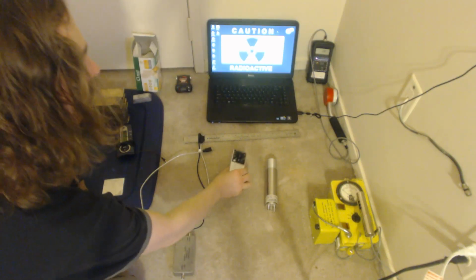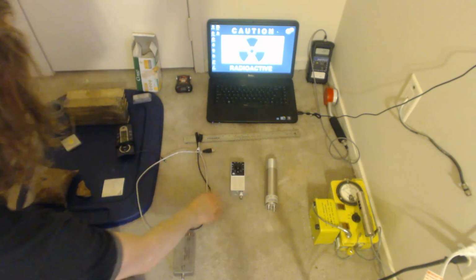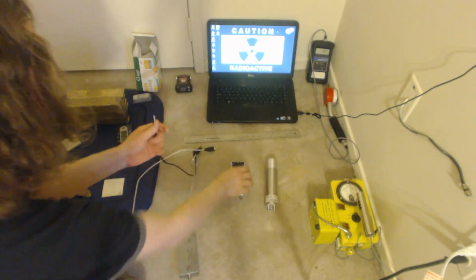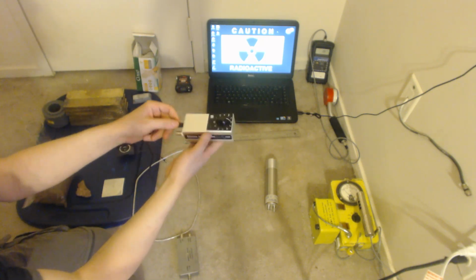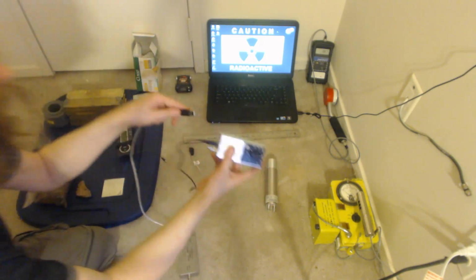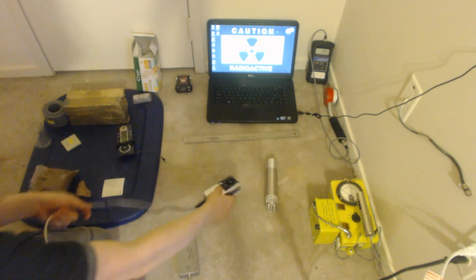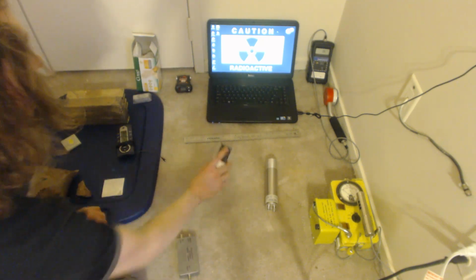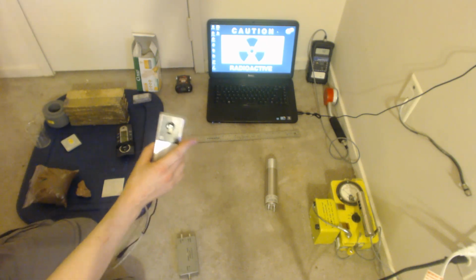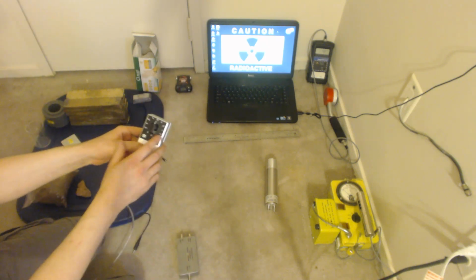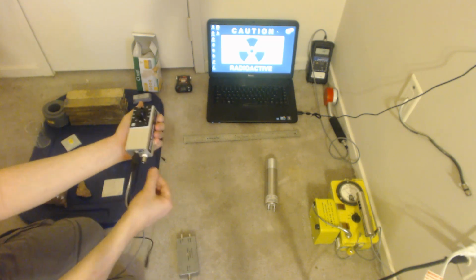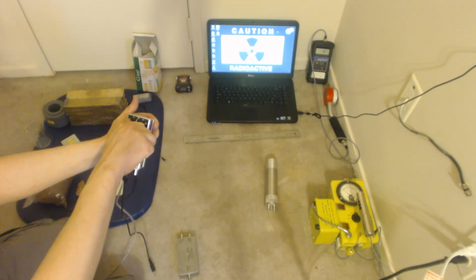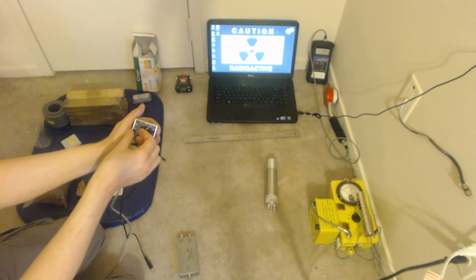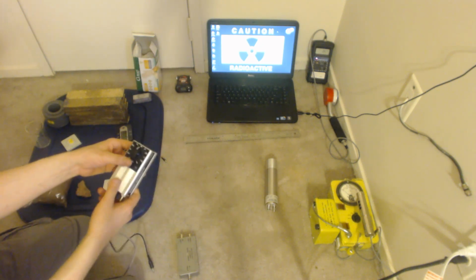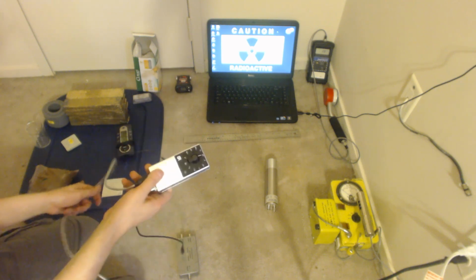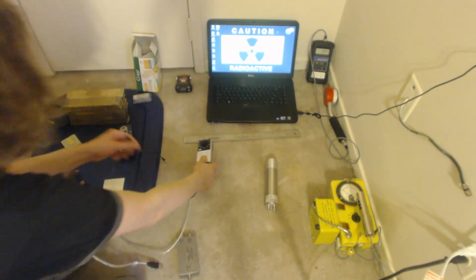Okay, let's connect everything up. First off, let's connect the unit here. We're going to take the audio cable, plug it into the Gamma Spectacular. We're going to plug the USB cable into the Gamma Spectacular. Make sure the power is set to off. If you have everything connected to it, then that's fine, but you really don't want to have this not connected to anything with the power already on. It's not good for the unit. And in fact, you should always have this off before you plug it in anyway. Never plug in electronics when they're set to the on position. It's just not very good for them.